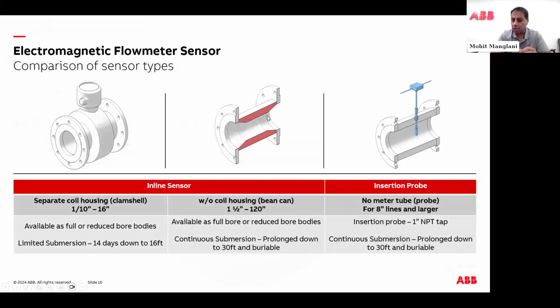There are 3 types of mag meters. One of them we call a coil housing mag meter, clamshell. I actually have a typo there. We have something called a bean can, where basically you have a solid piece of pipe, and you're able to run flow through there as well. The nicer thing about the middle one, without the coil housing, is that you can handle submergence better.